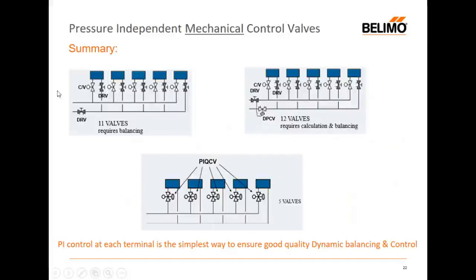And that's inefficient. And it's inefficient because really DRVs were developed initially for constant volume systems, and now they're being applied in a variable flow system. So then what can we do about that? Well, you could, if you wished, use a conventional balancing valve and a control valve, and then limit the pressure seen by the control valve with a differential pressure control valve. That might seem a good solution because I'm maintaining a known fixed delta P on the branch, which means I can size my control valve against it.